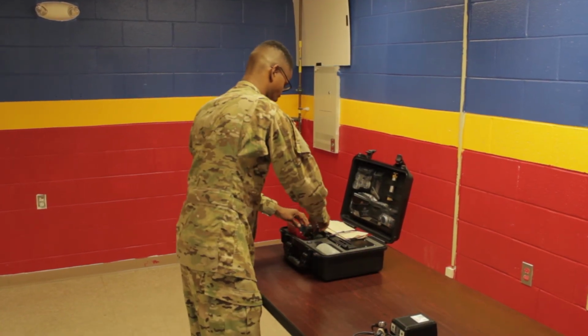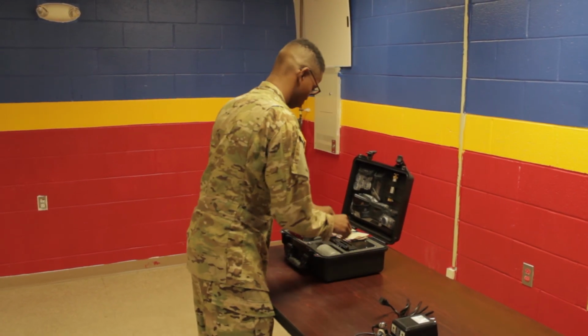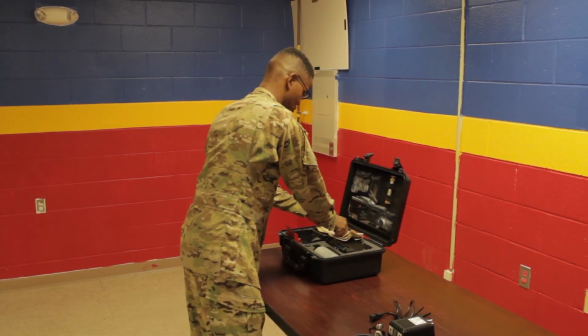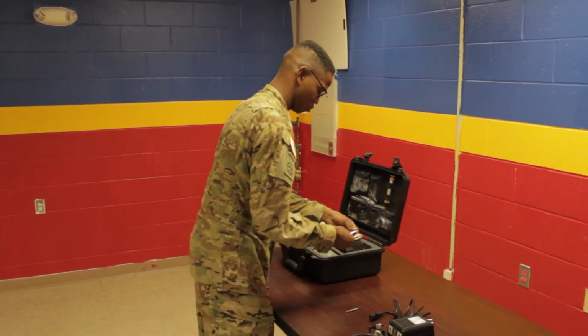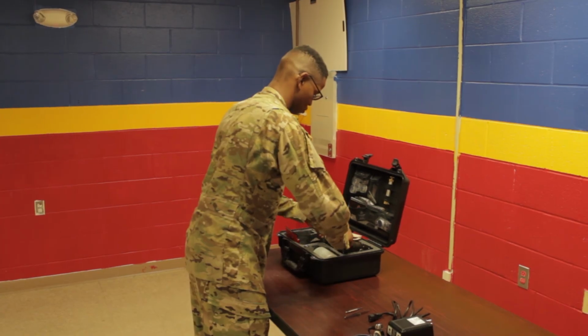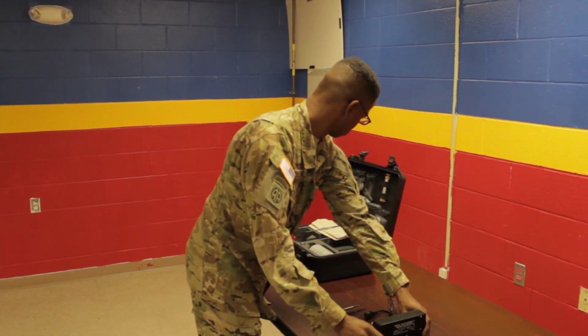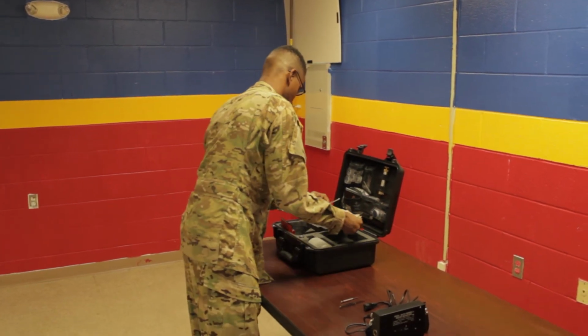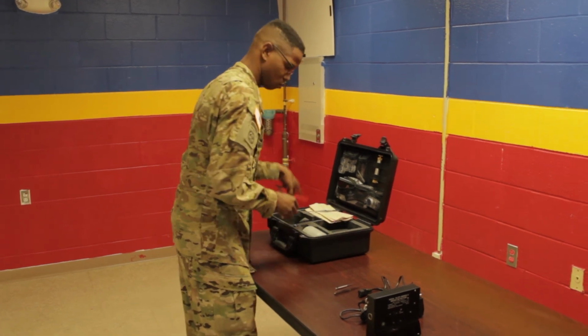The Aqua Glo Series 5 water detector kit determines the degree of undissolved water content in the fuel. To ensure accurate free water detection, the Aqua Glo detector kit must be assembled for operation and calibrated before each use.